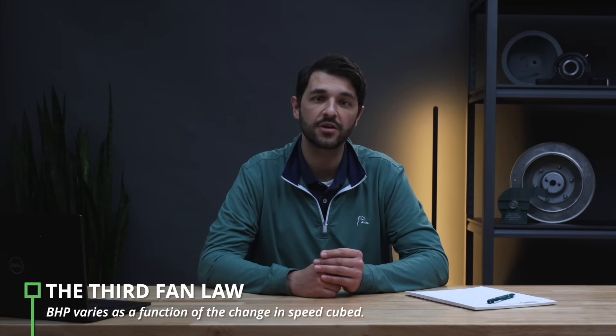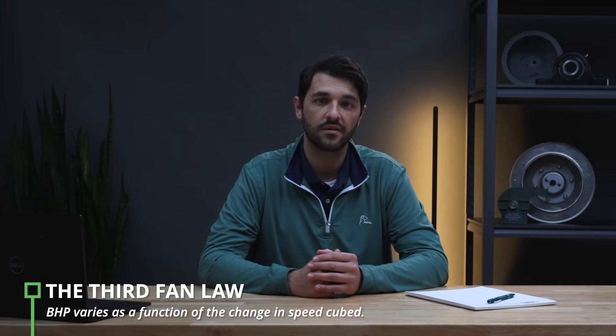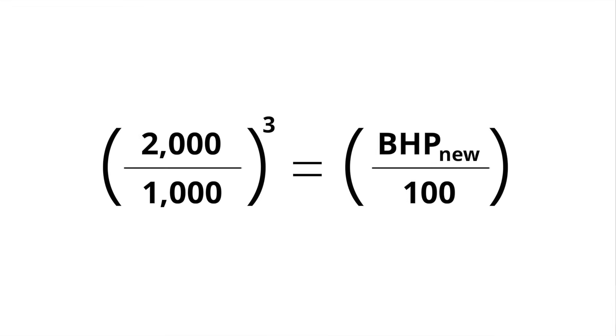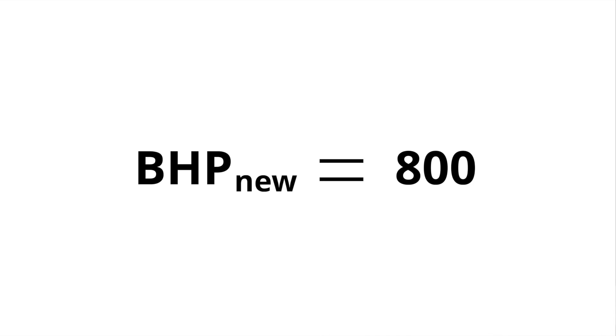The third fan law describes how brake horsepower changes in response to a change in speed. Here, the horsepower changes as a function of the change in speed cubed. This exponential impact on power consumption is useful in determining how much headroom a fan assembly has for speed increase before exceeding the motor's rated capability. In our example, the equation is: (2,000 RPM / 1,000 RPM) cubed equals the new brake horsepower X divided by the old brake horsepower 100 — which solves for a new power consumption of 800 BHP.